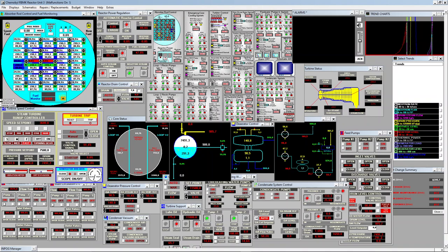Okay, you see the valve control signal is struggling to keep the pressure set point at 7500. And I will increase power set point to 100. Okay, so everything goes fine. I will make a test. I will see if the reactor can work with only one recirculation pump in each loop.